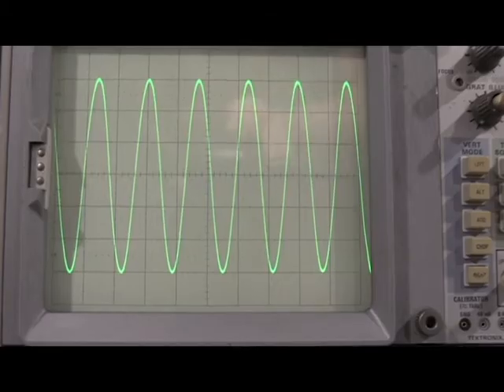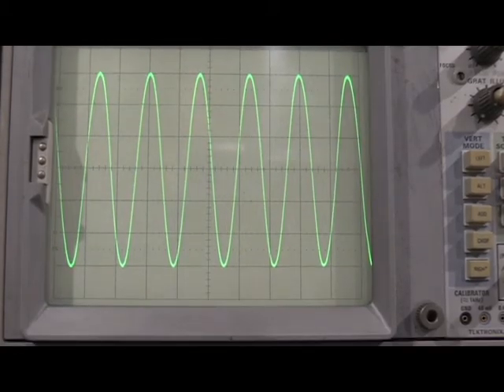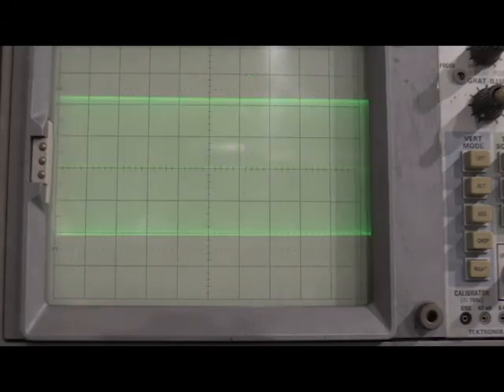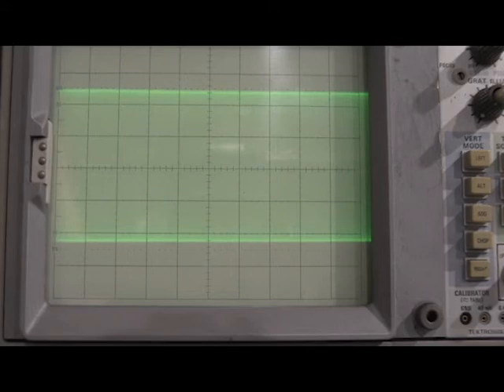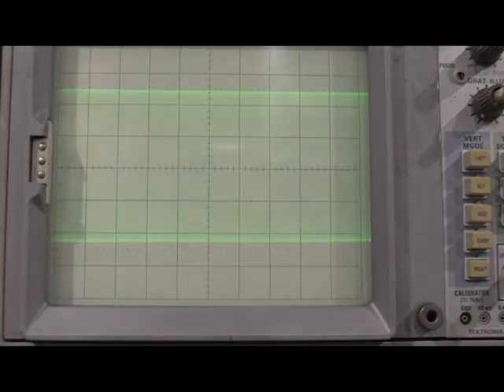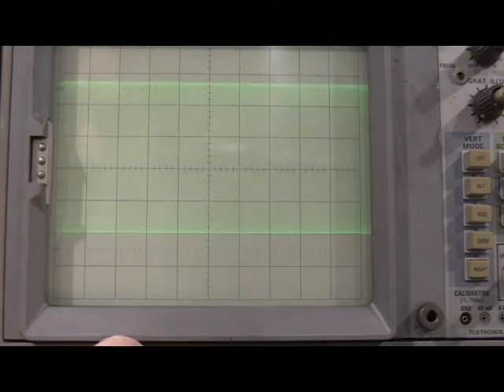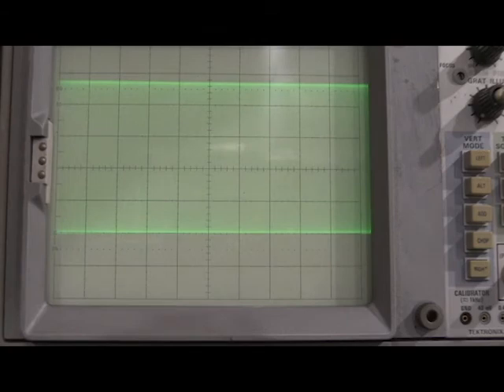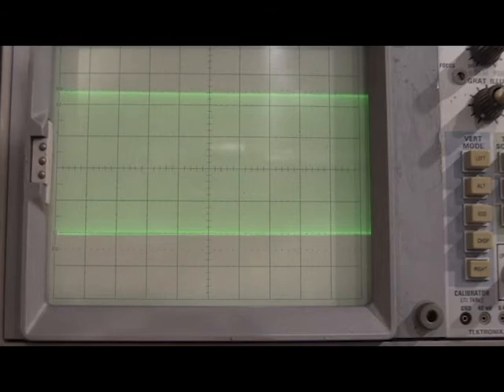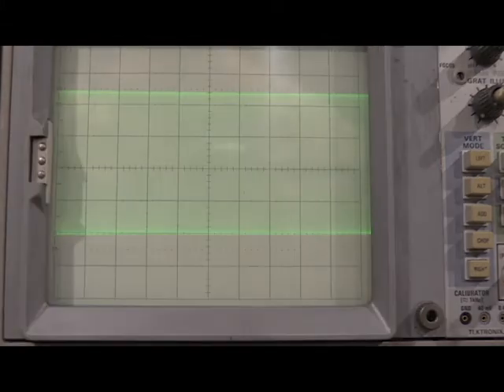No problems with vertical bandwidth. And the service manual has me testing both compartments, left and right. So this is the exact same test on the right side. Right side's actually a pretty good match. That is also 4.2, and we're getting 117 out of the right side channels. So they are within a megahertz of each other. So we should be good.